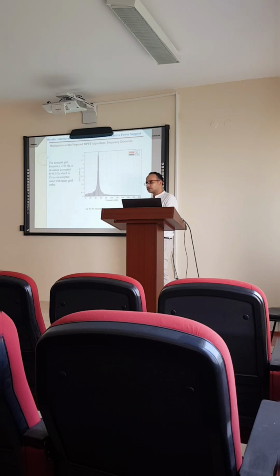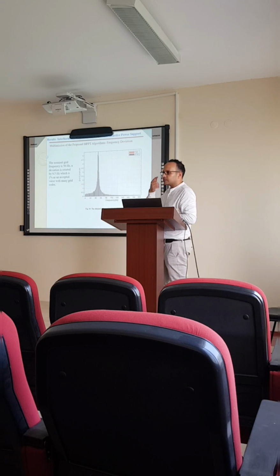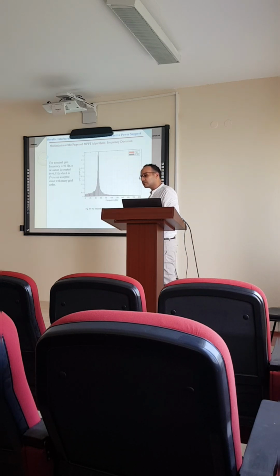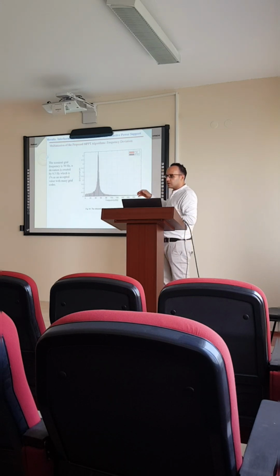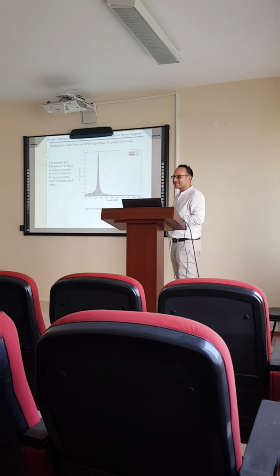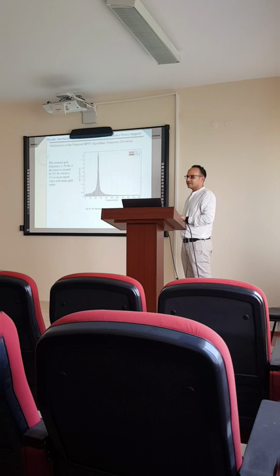You should adapt the proportional part. Yes. You should adjust the active power. You should follow the grid code. There is a curve. They give a proportion between the active power and the frequency deviation. If the system has the inertial response, in case of a frequency deviation, for example, for 1 Hertz, it corresponds to, if you follow the curve, assume that it corresponds to 1 kilowatt. If you reduce the active power rate, you should also reduce the proportional part, then you will see that the system will be fixed. Yes, it's a good future thing. Maybe it's a good idea.